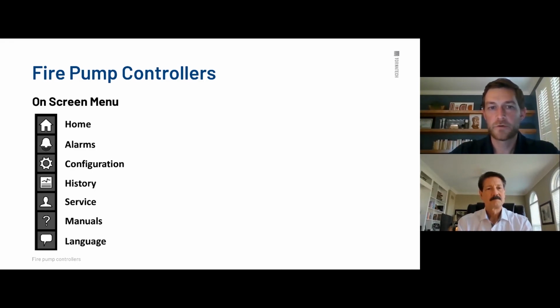The second one down below is the alarms. That's going to be any active alarms. If your pump's on demand, if you have unhealthy voltage, whatever the controller is trying to tell you, it's going to be in that alarm section. Then we have the configuration page. That's where you're going to be setting your pressures. If you want to enable automatic shutdown, that's where you're going to get into the advanced menus too for testing of the alarms. You don't test the alarms from the alarm page on here. This drop-down menu to alarms only sends you to active alarms. So in order to test alarms, you go through configuration, and it's in the advanced section.